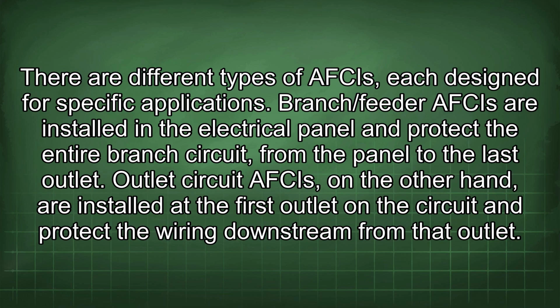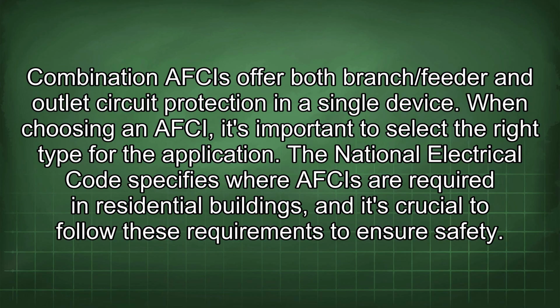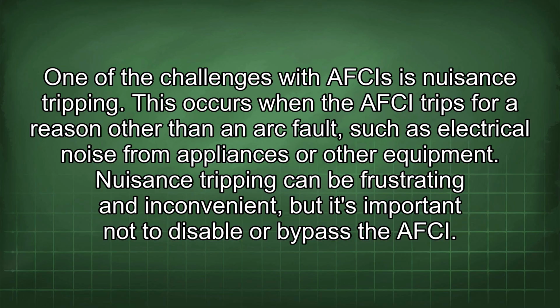Branch/feeder AFCIs are installed in the electrical panel and protect the entire branch circuit from the panel to the last outlet. Outlet circuit AFCIs, on the other hand, are installed at the first outlet on the circuit and protect the wiring downstream from that outlet. Combination AFCIs offer both branch/feeder and outlet circuit protection in a single device. When choosing an AFCI, it's important to select the right type for the application. The National Electrical Code specifies where AFCIs are required in residential buildings, and it's crucial to follow these requirements to ensure safety. One of the challenges with AFCIs is nuisance tripping.